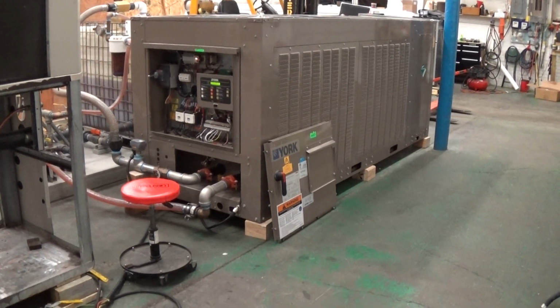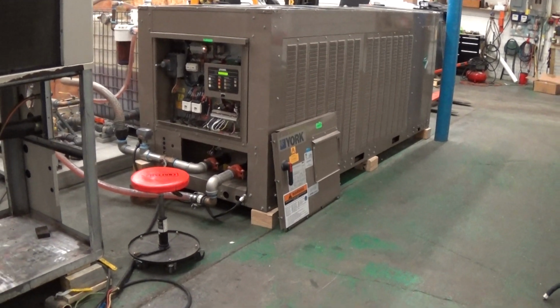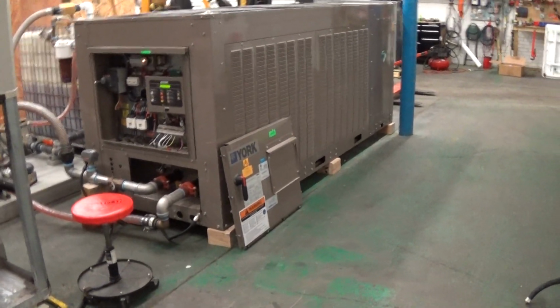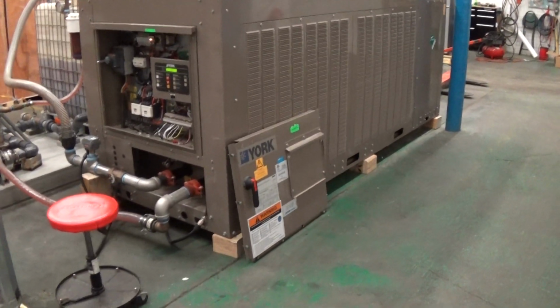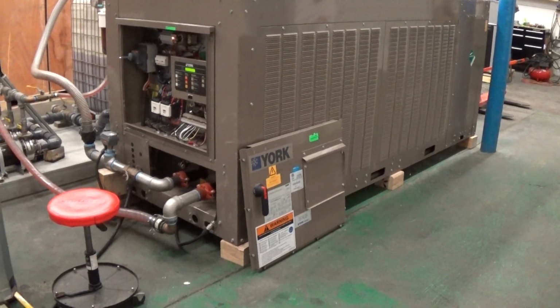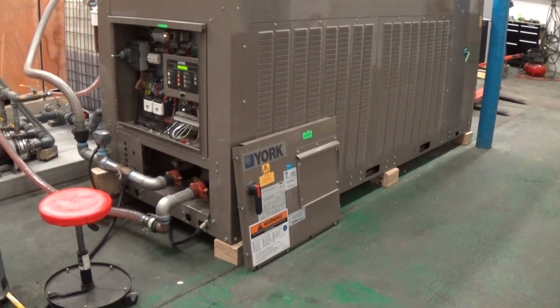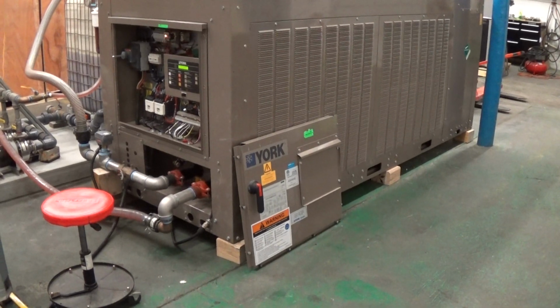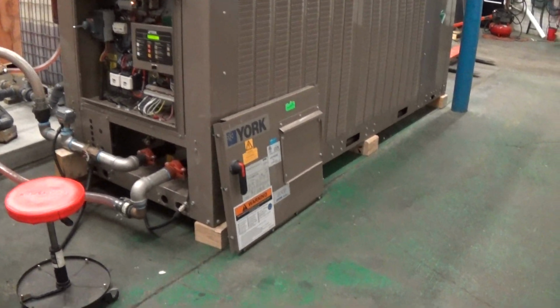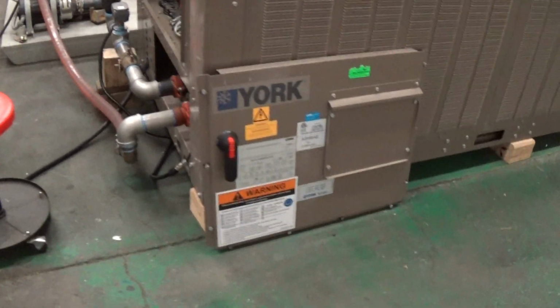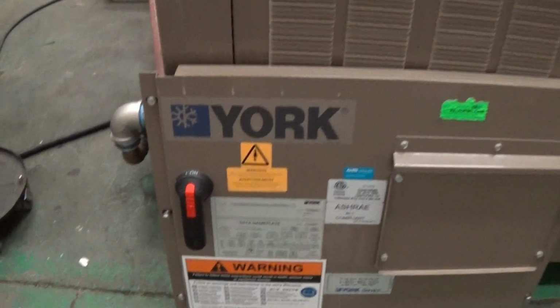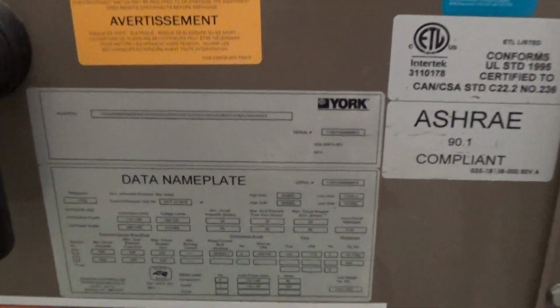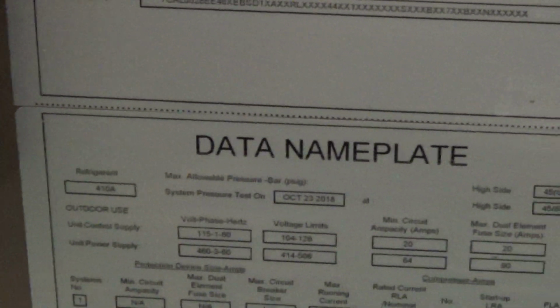Sometimes we'll bring and store units into our 13,000 square foot facility here in Clinton, Massachusetts, as we've done on this one here. This unit, as I said, is configured with a low temperature option, so it can go down into the 20s as far as fluid temperature or glycol temperature goes. It's an R410A chiller. The model for this unit, if you can kind of see it there, it's very small, there you go, YCAL 0028 for 28 ton.